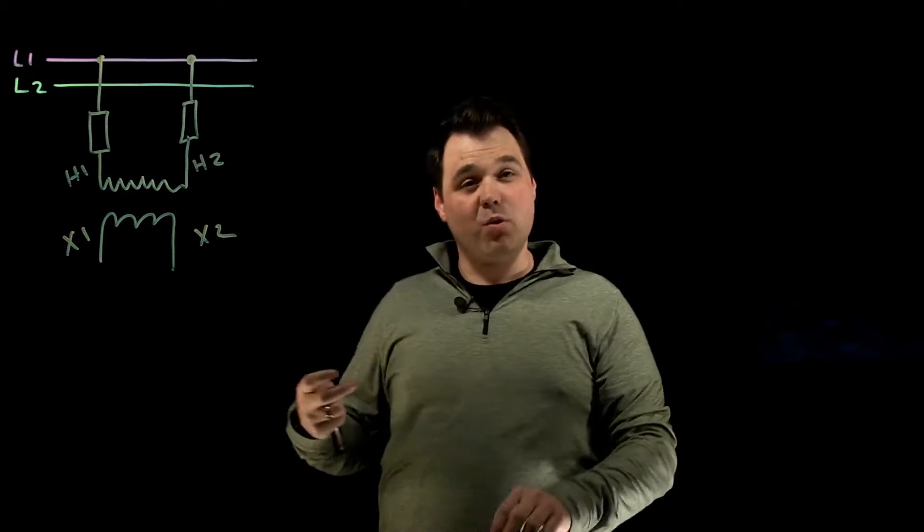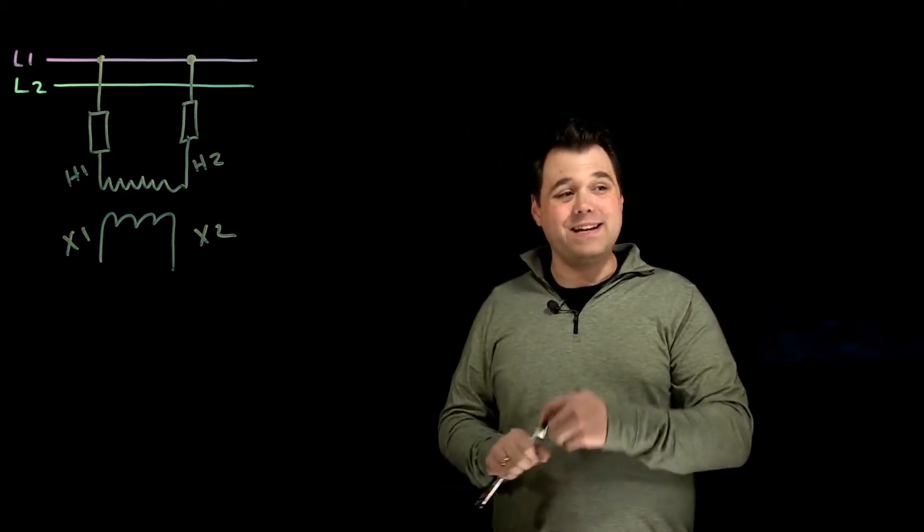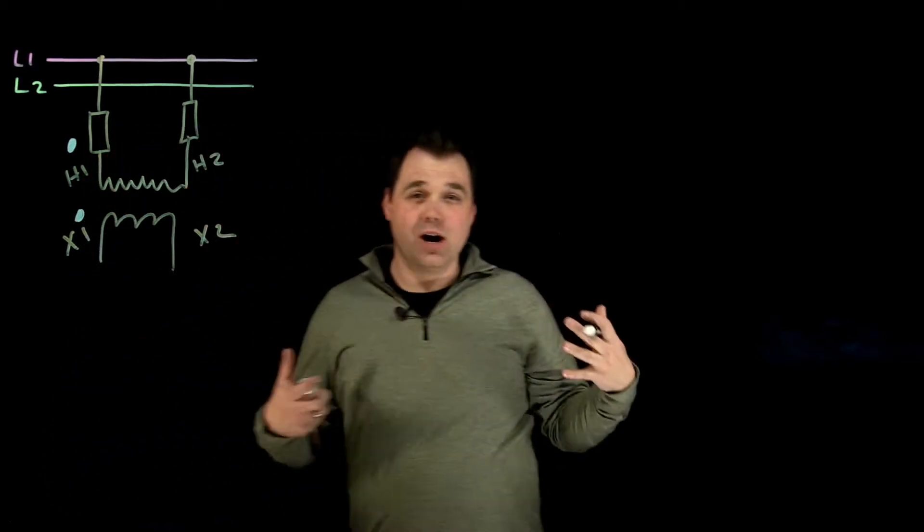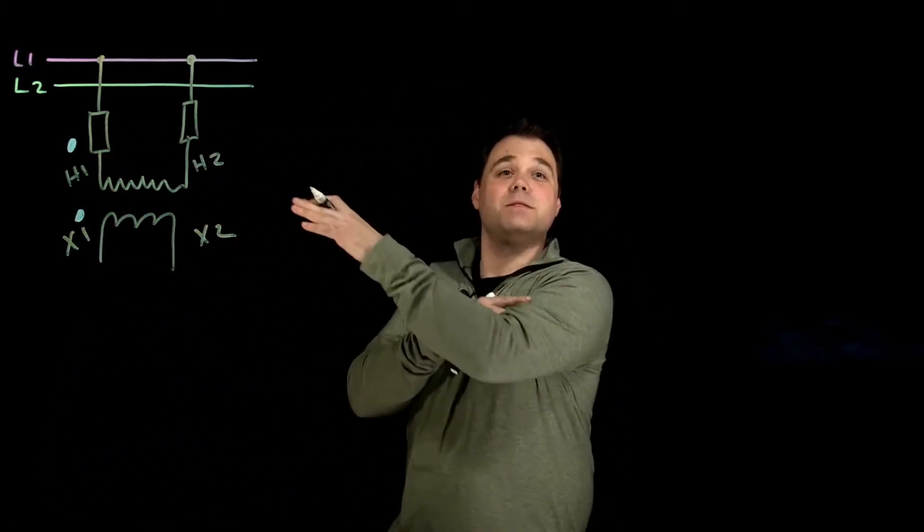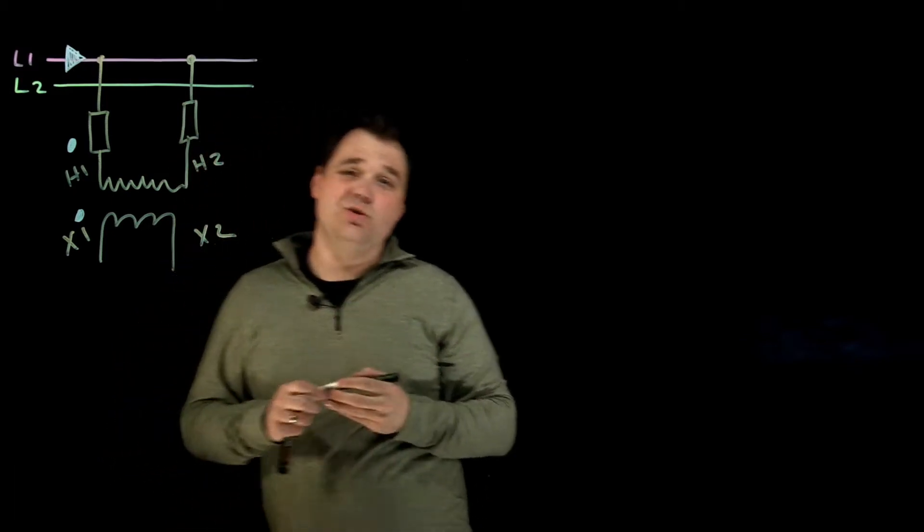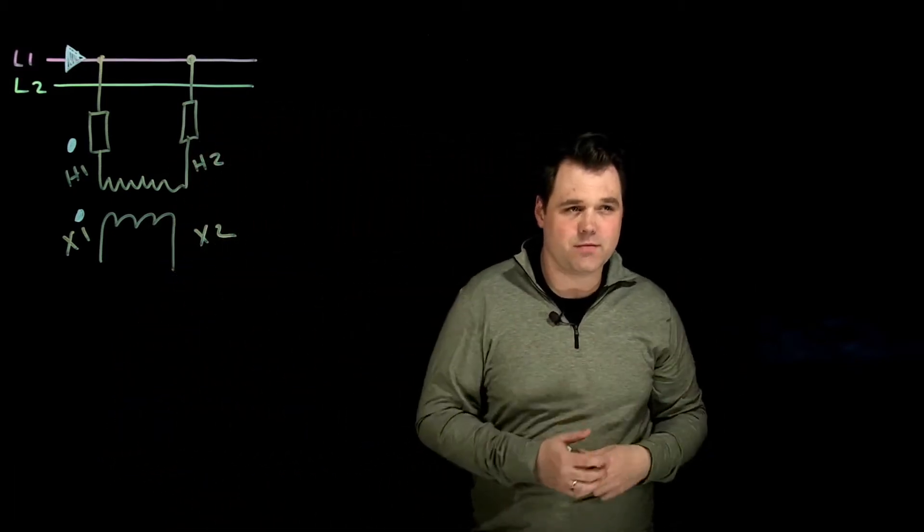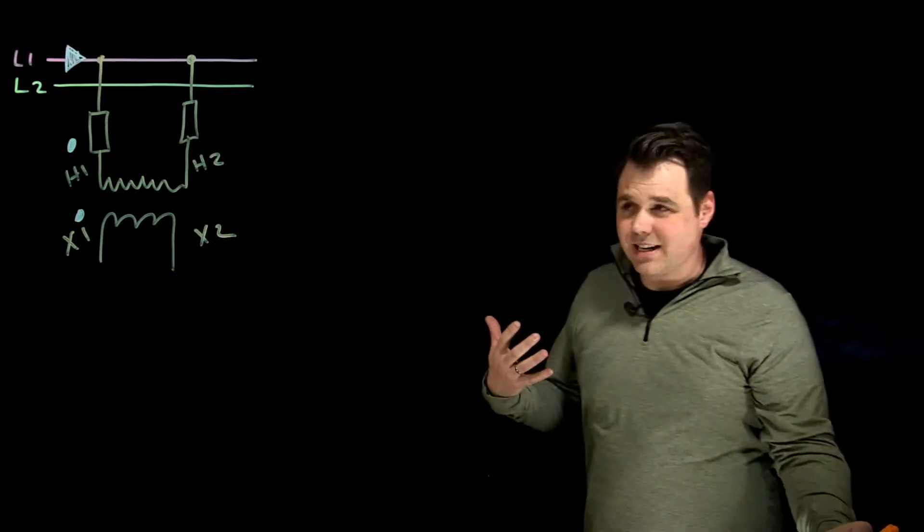One other thing that is important to note is they will always have a white dot on them, or often a big white dot. The white dot is meant to go towards the supply or towards the source. So current flows into the white dot, ideally if the current is coming from the source. That's the idea behind that white dot.